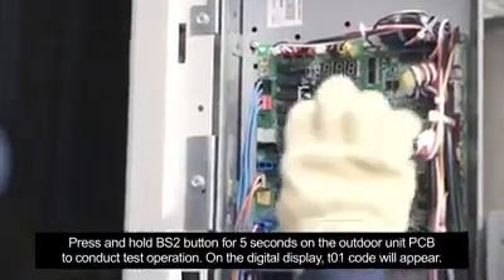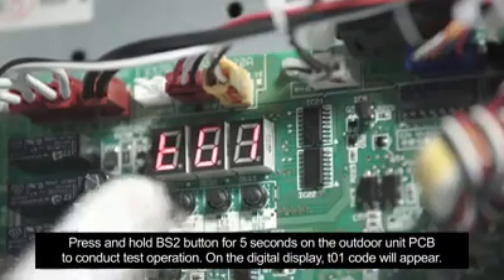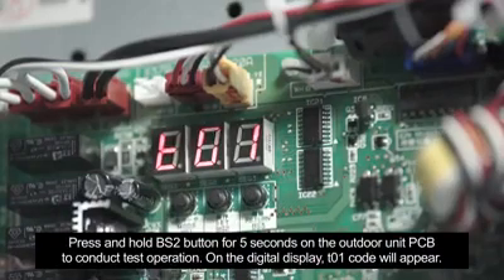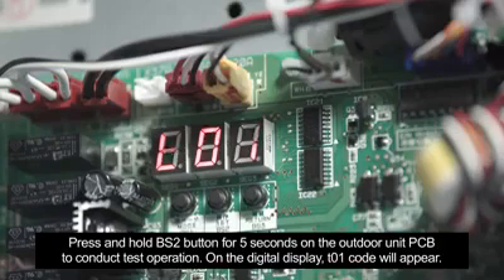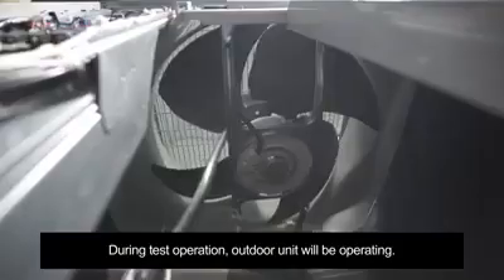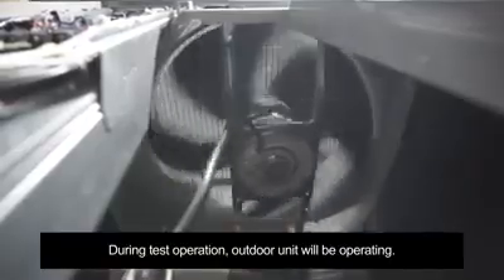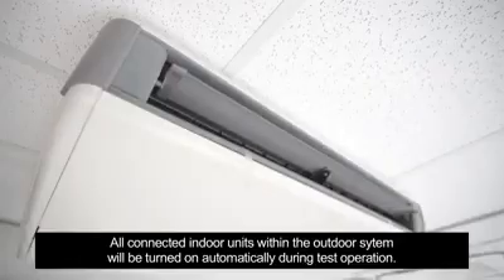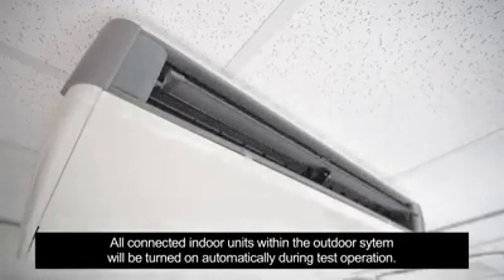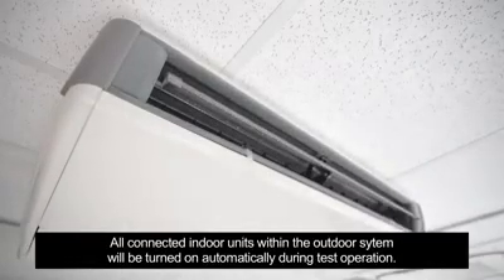Press and hold BS2 button for 5 seconds on the outdoor unit PCB to conduct test operation. On the digital display, T01 code will appear. During test operation, outdoor unit will be operating. All connected indoor units within the outdoor system will be turned on automatically during test operation.